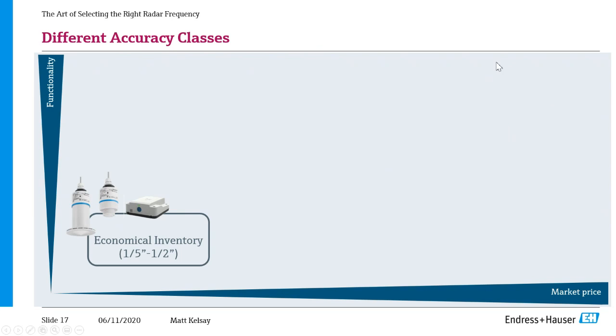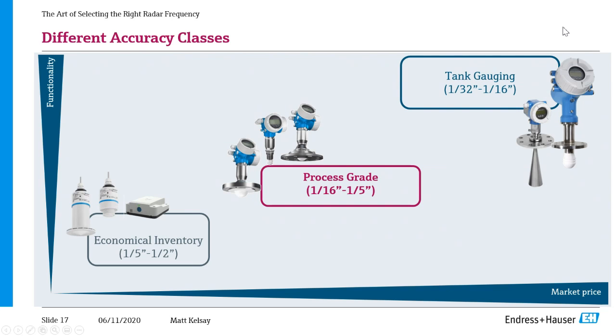It's important to note that there are different classes of radar based on the application and customer needs. If you go to the next, this could range anywhere from a very economical radar, something like a little battery powered unit that's meant for remote monitoring, where you're going to get lower accuracy, but it comes at a much lower price. If you go to the next, you see a process grade radar, which is most common in most industries that we cover. If you're looking at a storage tank or a reactor, this is in that range. So you get good accuracy, mid-level price. Go to the next is the highest level of accuracy, or tank gauging style radars, where you've got a large diameter tank, so a small change in level has a big impact on volume. You need that highest level of accuracy.